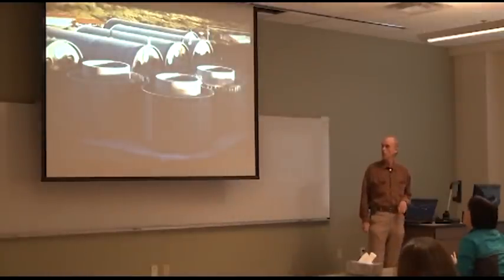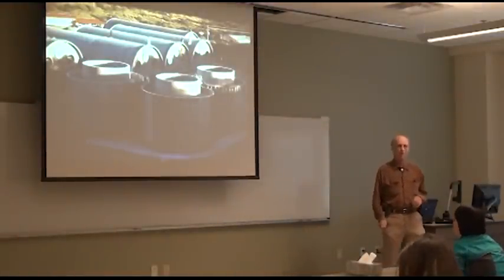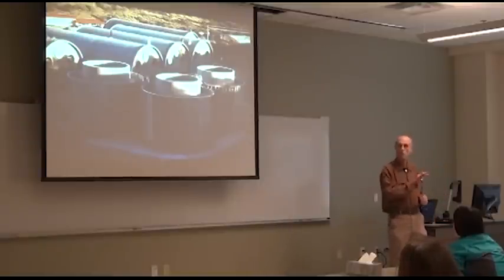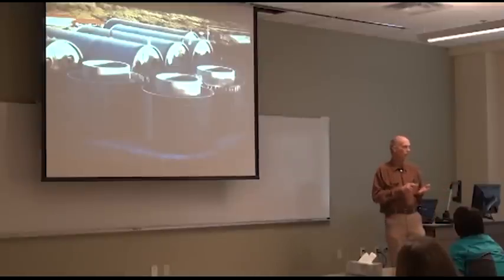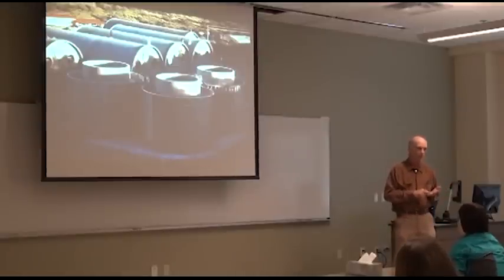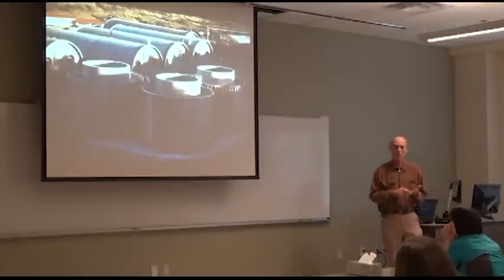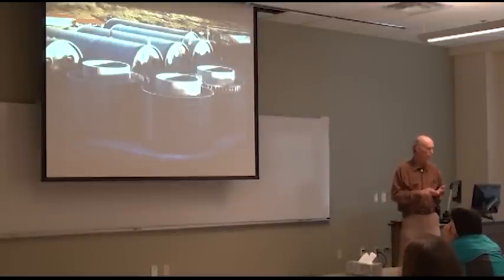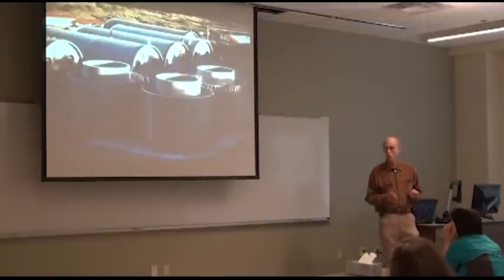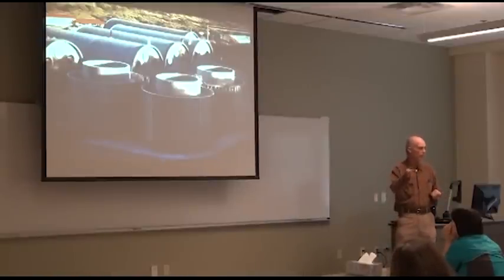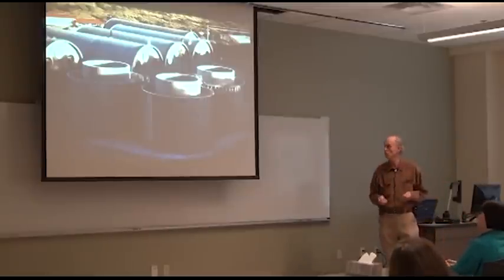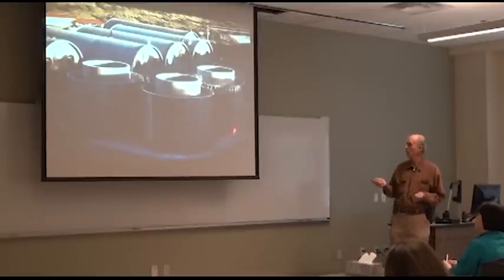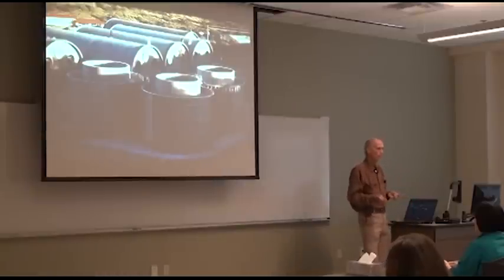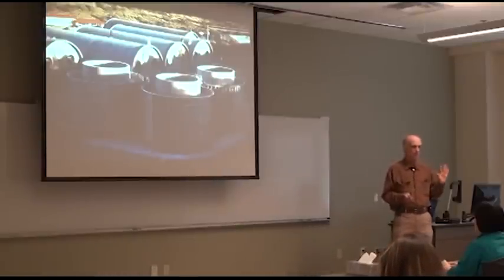And here is a picture of the energy center, which I mentioned before. Energy was supplied from outside into Biosphere 2. We have our own electric power generators. We had three of them, 1.5, 1.5, and 2.25 megawatt generators. We had compression refrigeration cooling, using ammonia chillers to produce the cold water that I mentioned before that was necessary to cool the space. And we had evaporatively cooled water. These are the cooling towers that cooled water evaporatively. Biosphere 2 used a lot of energy.